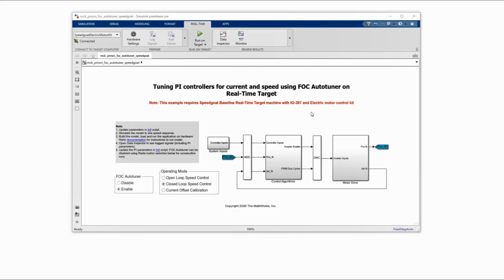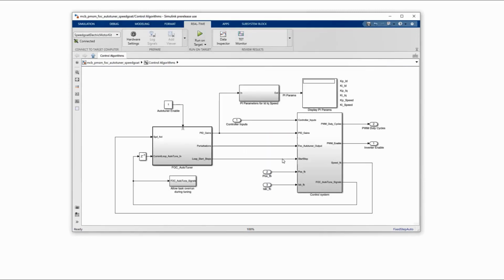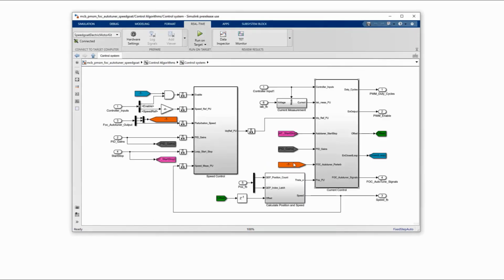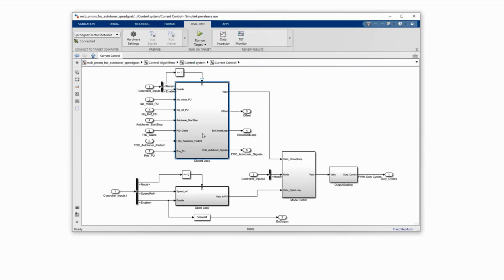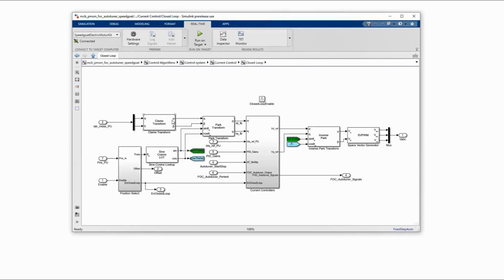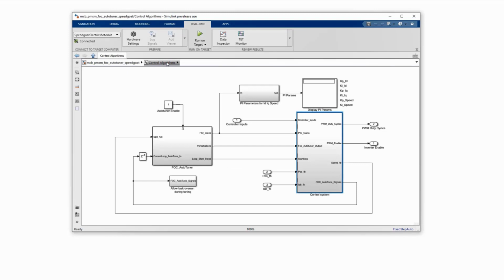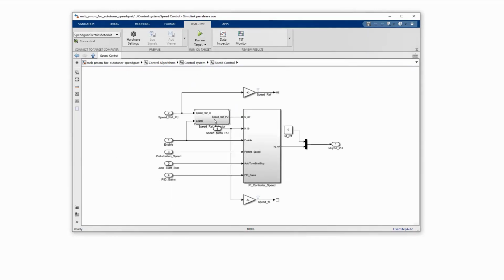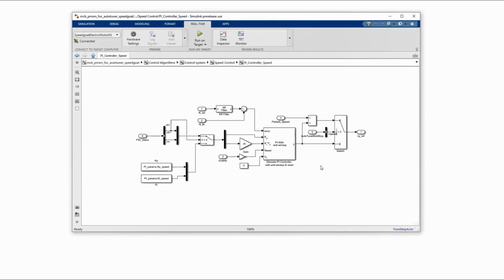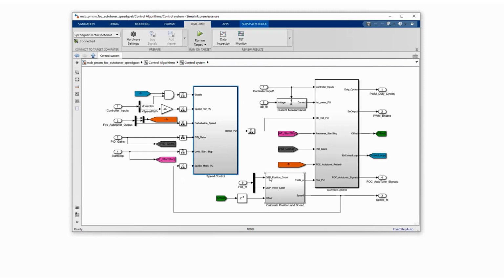In this demo, you can tune the current inner loops and the velocity outer loop of a brushless DC motor. This is done using a field-oriented control auto-tuner from motor control block set. This model uses field-oriented control, so in the current loop, we will see the Clark and Park transforms, as usual. But also, now we'll have the field-oriented auto-tuner block that will be able to insert perturbations, and it will also be able to access sensor data in order to calculate the gains for the PI control loops.